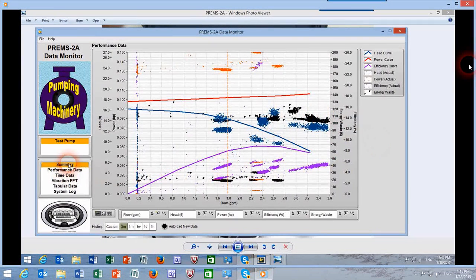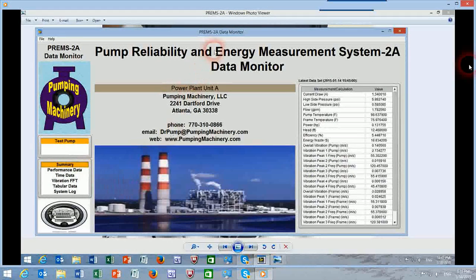Let's look at a summary screen. The summary screen basically shows your project, let's say in this case it's power plant unit A. On the right-hand side of the screen are current data as it was taken at the last measurements: current, high pressure, low pressure, let's say discharge and suction pressure, flow, temperatures, power, head, efficiency, energy, overall vibrations, and spectral vibrations. Several peaks come from FFT, fast Fourier transform, for the spectral analysis on vibrations.